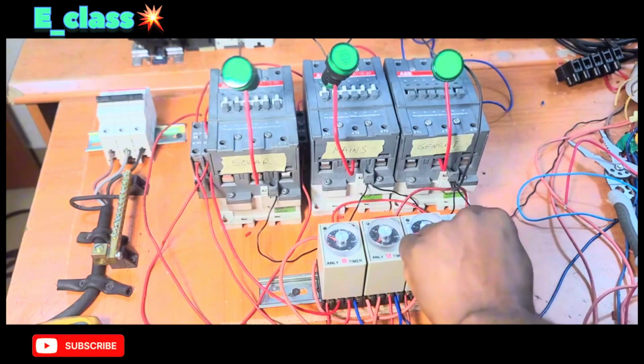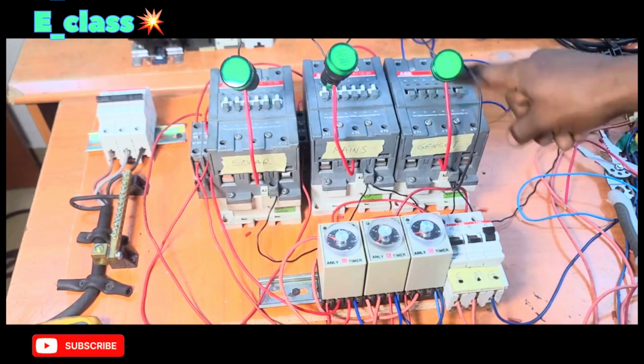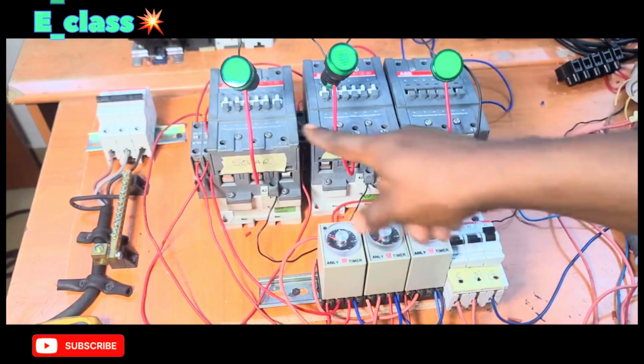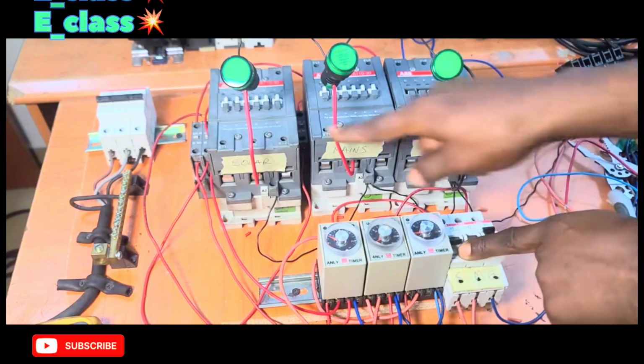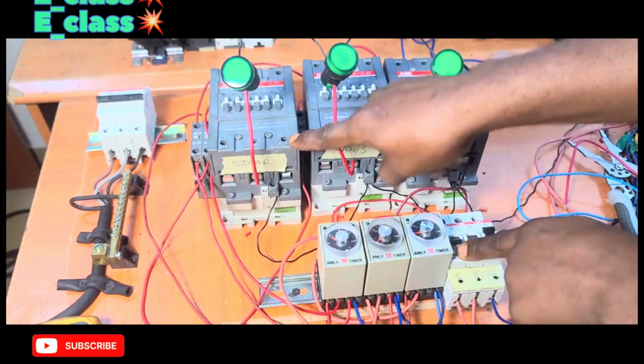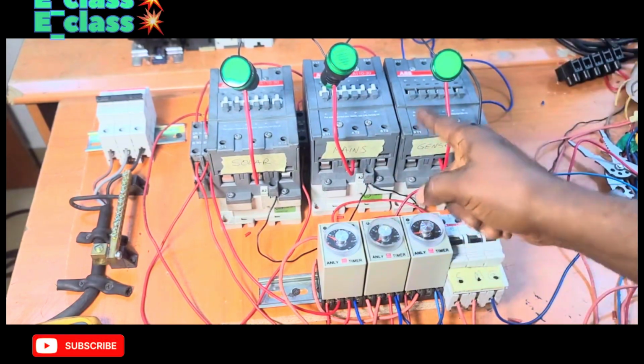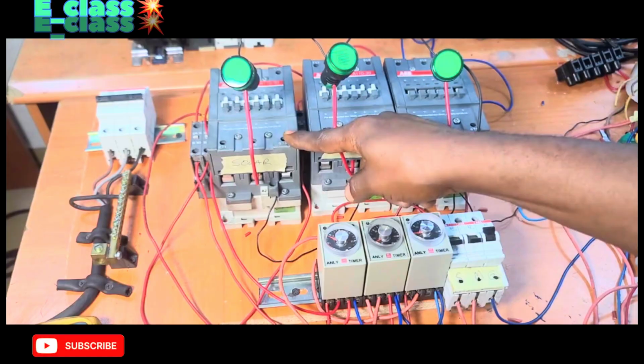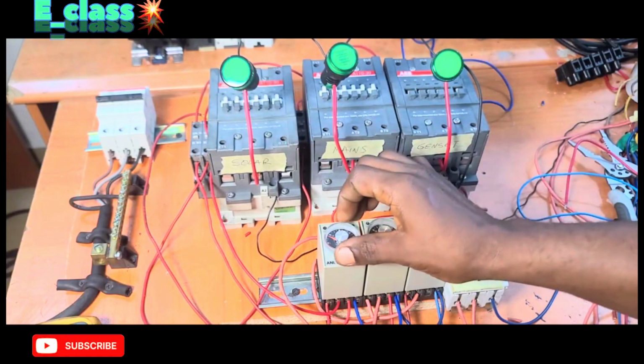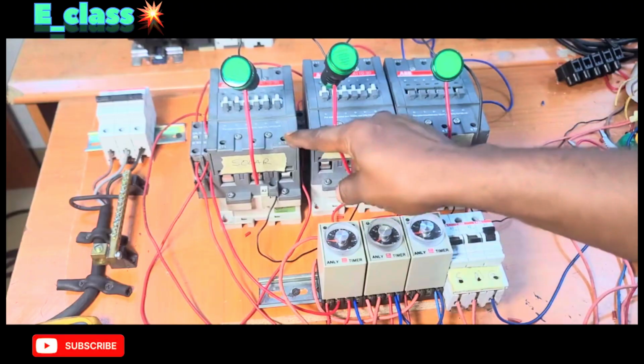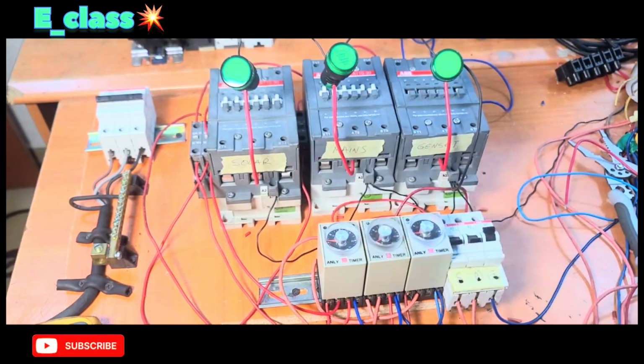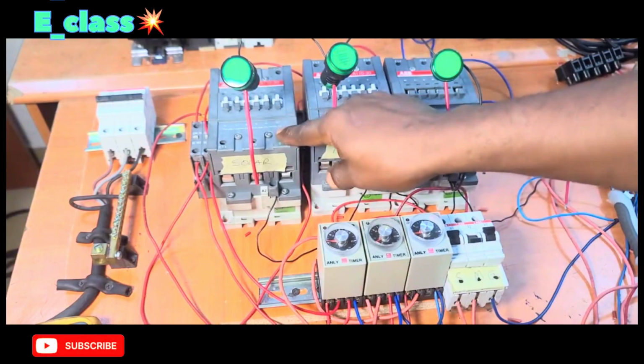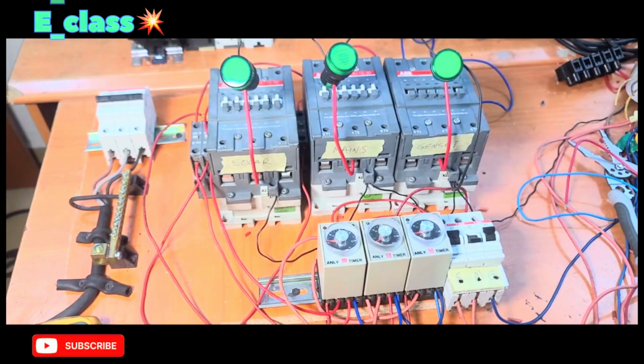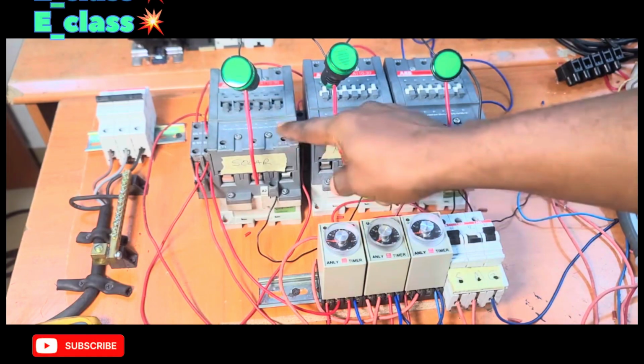Let us put it off again. You see, this one is up. This one is activated. All right? Now, when we put on this one, meaning that solar is up and active, what we want is for this one to cut off. It's supposed to disconnect from the load immediately, while this one will connect after some seconds delay. Let me reduce this time, it takes so long. After some seconds delay, this one should be able to close. But it's not working that way. Now, solar is up and active. You see? So it was after the delay only that this one de-energized.